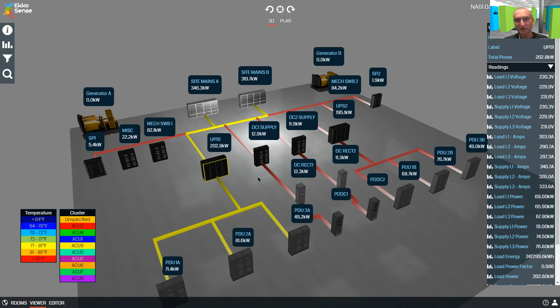This is a simple way that you can configure your site power and then define which systems are supplying which rooms. So if you've got different UPS systems, for example, dedicated systems supplying certain rooms or floors and facilities, that's how you can capacity manage between different rooms. Any changes that you make in a particular room will be reflected in all the other rooms because it's all held together at this site level, how you've constructed the site power distribution map, giving a good view of how the power has been moving around the site.